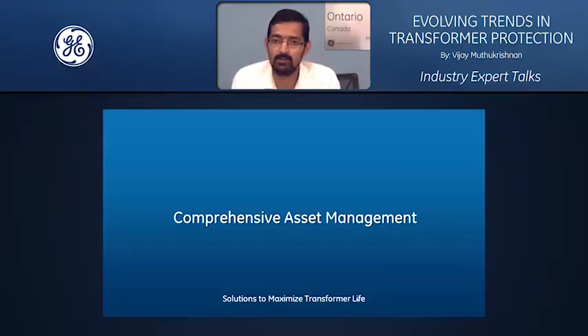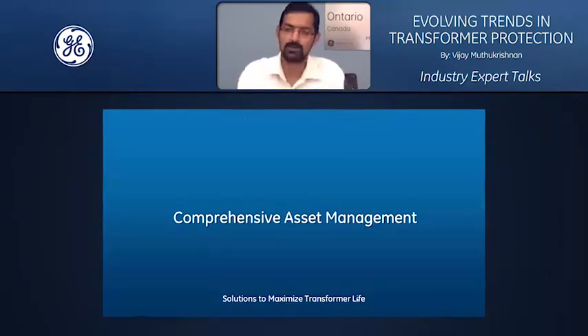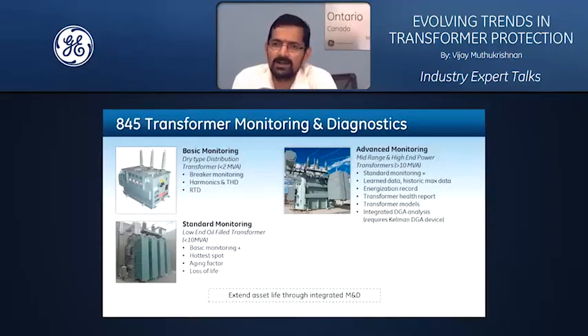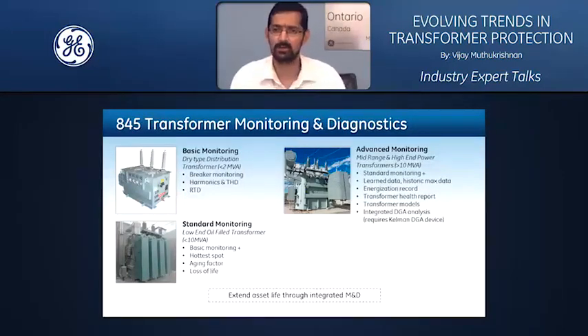Whereas the technology now allows you to do a lot more processing, a lot more data collection within the transformer protection relay. And if the transformer protection relay is watching the transformer 24/7, 365 days continuously, the power of collecting and interpreting the data and using that for asset management will be very valuable in terms of extending the life of the transformer. That's where the next trend of transformer protection is heading: towards asset management. What are the monitoring and diagnostics functionalities you have within the device? You can have a simple protection relay with basic monitoring functionalities, like monitoring aspects of your breaker, some level of harmonics, and some basic RTDs for temperature monitoring.